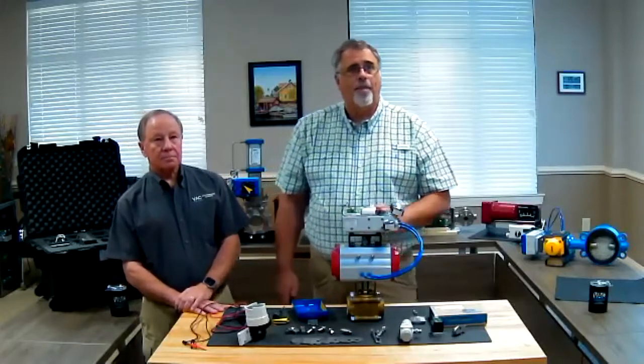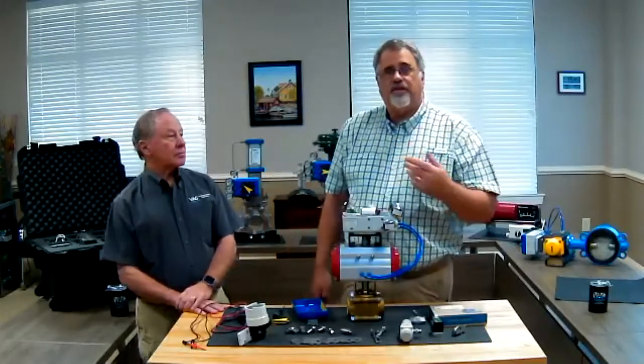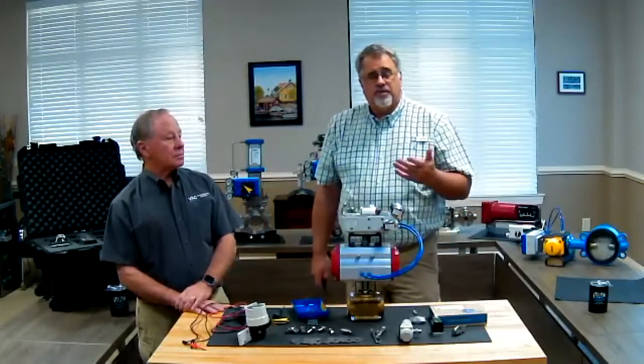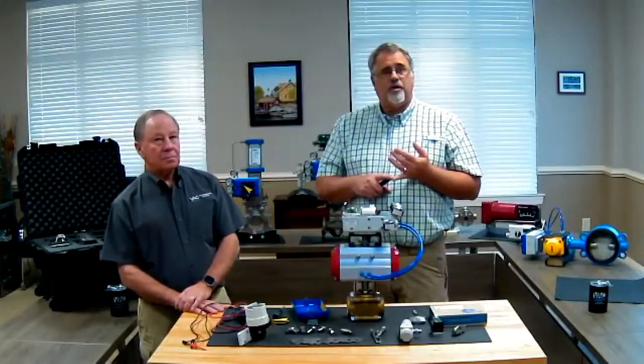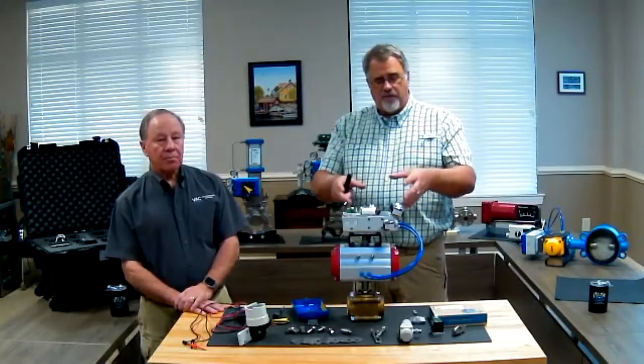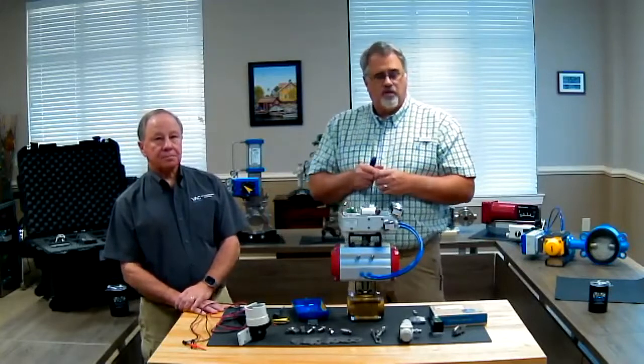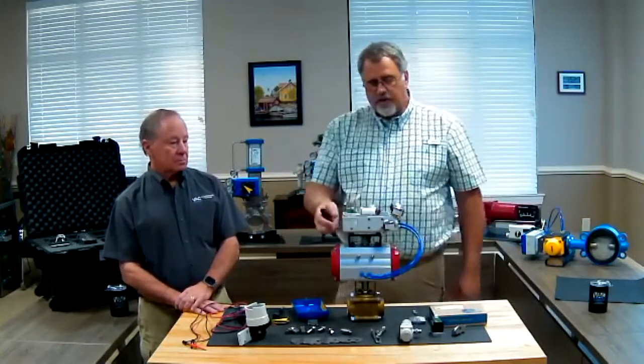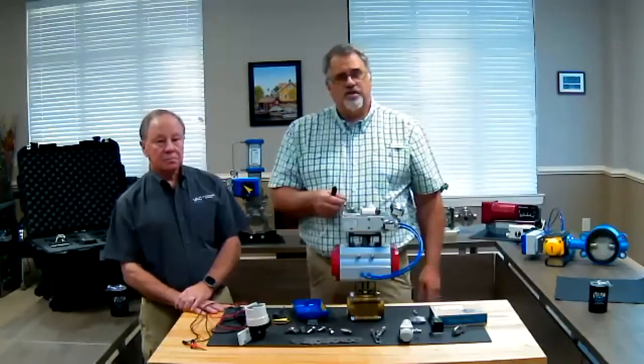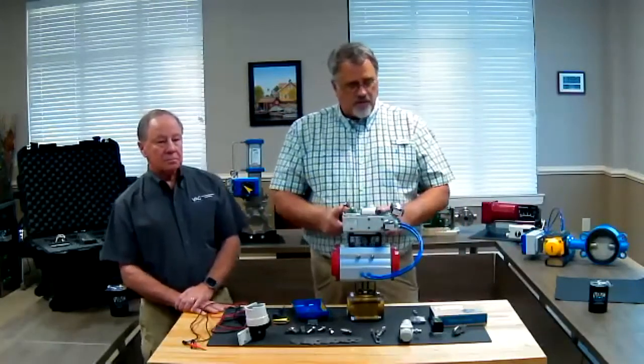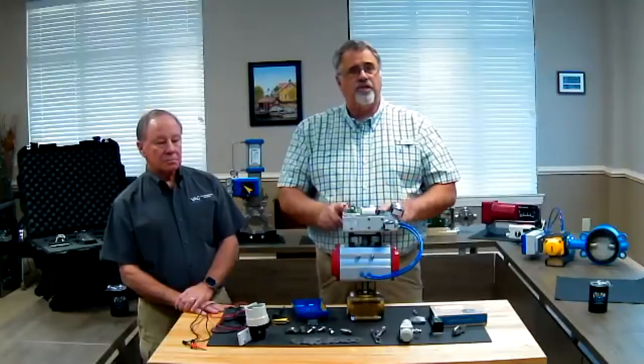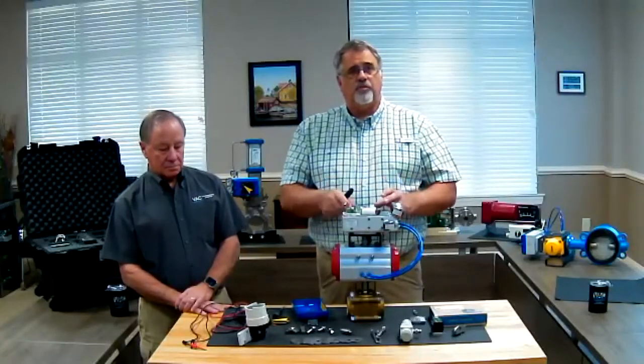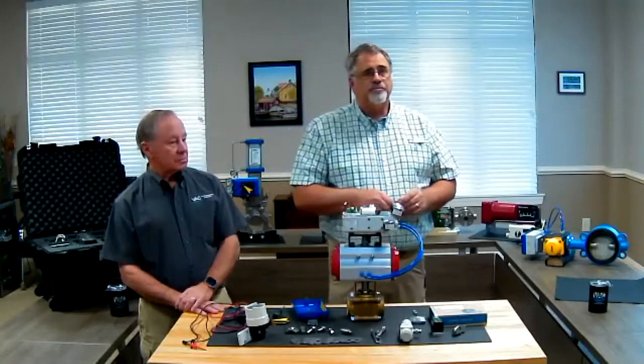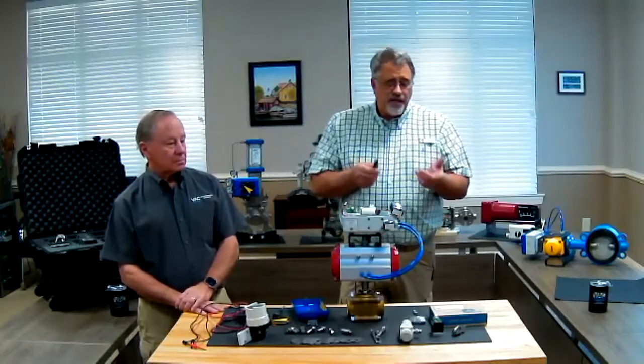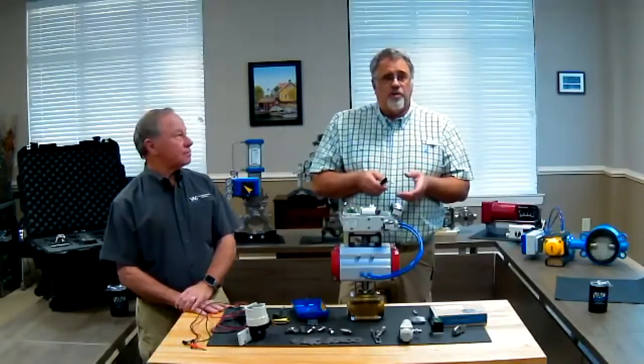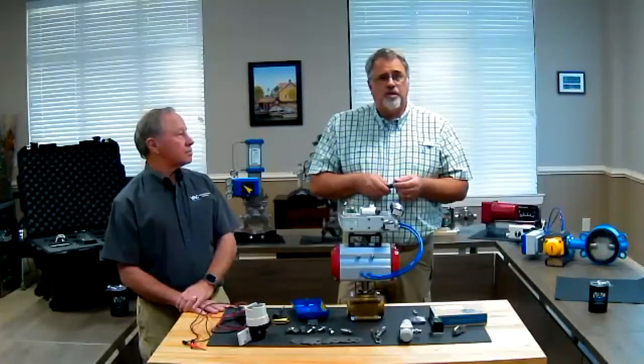So what does all of this add up to? Reduce downtime. If you can replace the parts in the positioner on the valve without having to take the whole positioner off, you don't have to break all your air connections. You don't have to break electrical conduit connections. You can keep the positioner on the valve, replace the damaged components internally, and return it to service very, very quickly. Typically, even in the field, you can repair one of these positioners in less than 15 minutes.